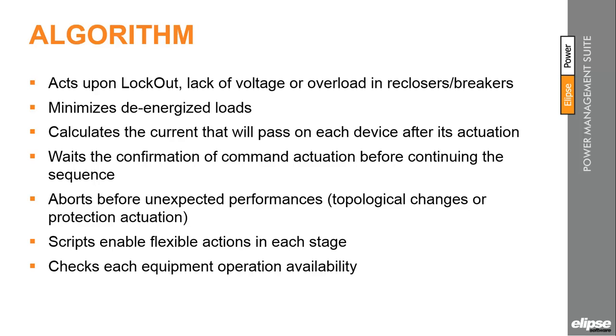Then, the algorithm calculates all the operations required to minimize the de-energized load. It aims for the highest amount of load or amperes that it can restore. In addition to that, it calculates the current that will pass through each device after its actuation in order to keep the system at stable operation and transfer the largest amount of load to other feeders. Then it waits for confirmation of command actuation before continuing the sequence. In other words, the device has to respond on whether the solicited action was indeed executed. This is a matter of reliability so that the operator has the certainty that the actions were really taken in the field.